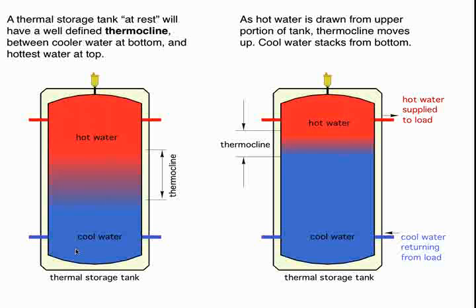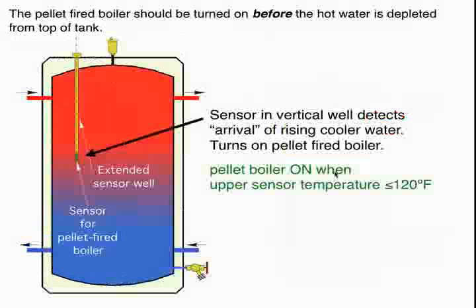The way we're going to do this is we're going to keep track of what's called the thermocline in the tank. Thermocline is basically the region between the hotter water at the top and the cooler water at the bottom. So over here on the left, if we have a tank that's essentially at rest and stratified, hot water at the top, cool water at the bottom, our thermocline is wider. Once we start a load and we start to take flow out of the top of the tank, the thermocline is going to tend to tighten up a little bit, and think of this tank as basically filling from the bottom up with cool water. The thermocline is rising through the tank, and we can use that movement of the thermocline in combination with sensor placement to provide our on signal for the pellet boiler as well as our off signal.